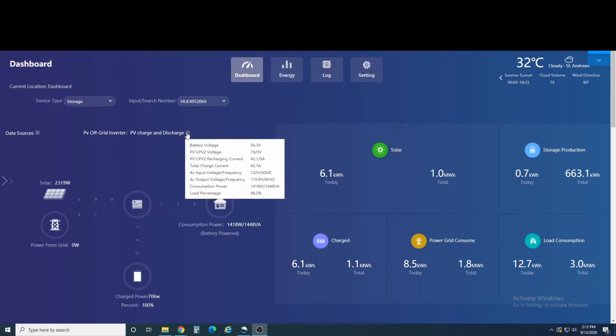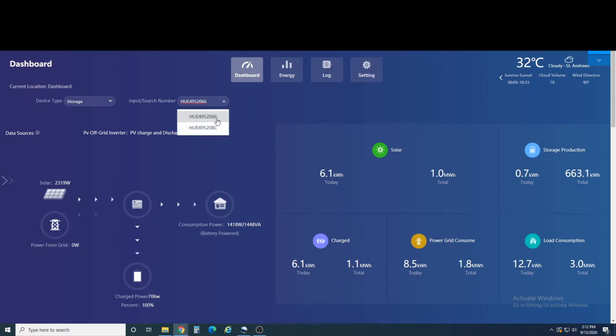Right now my battery voltage is 54.3, my PV1 and PV2 are at 76 volts. I've got 42 amps of charging current, 2319 watts of power coming through there, total charge current, input voltage, output voltage, and load percentage on this particular inverter at that time. I was consuming about 1400 watts, so about 48% of that inverter's capacity.